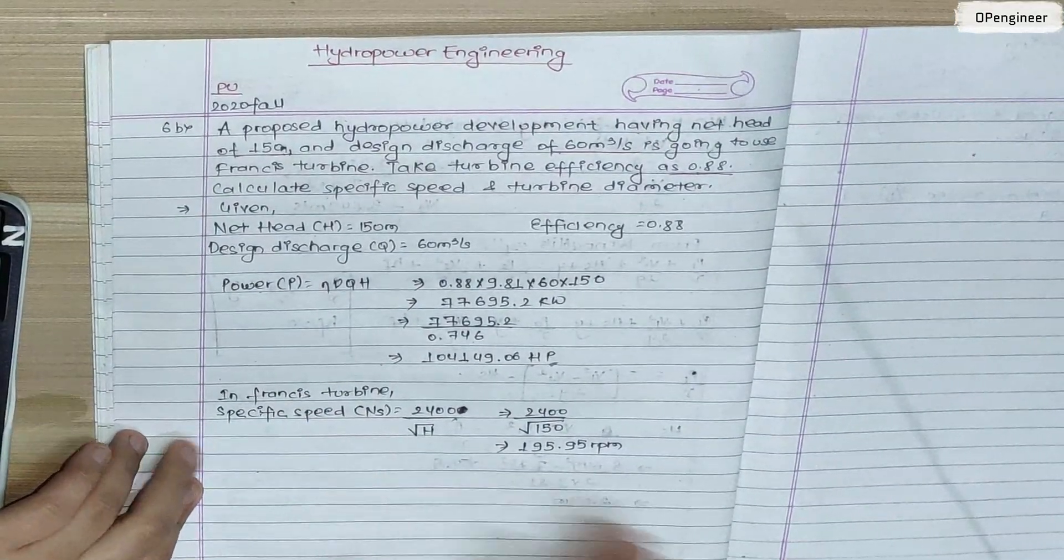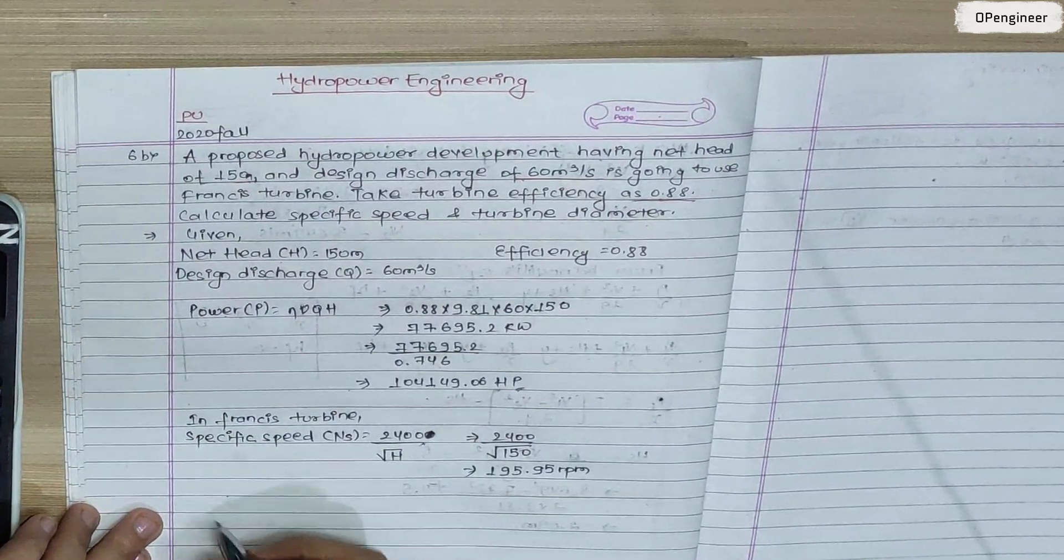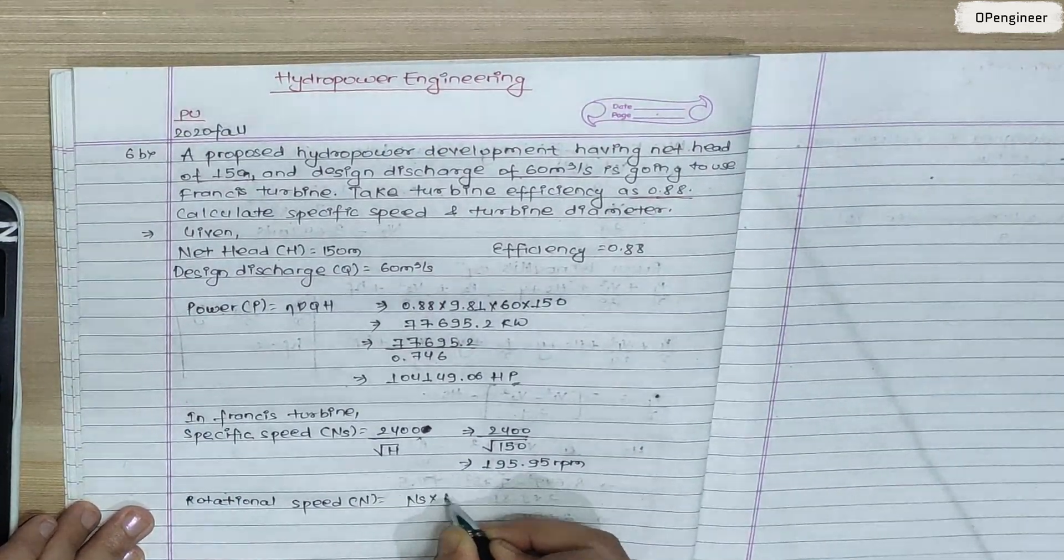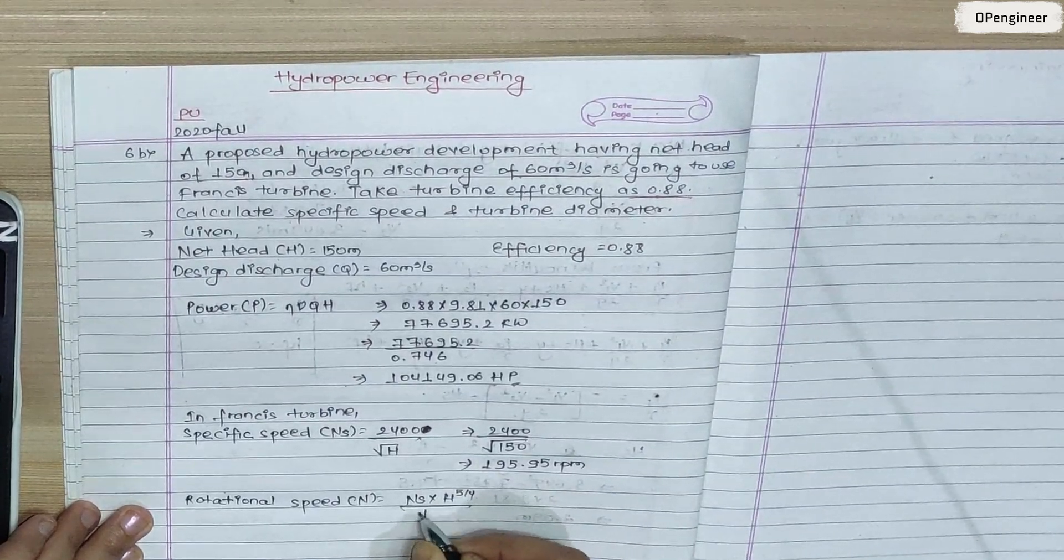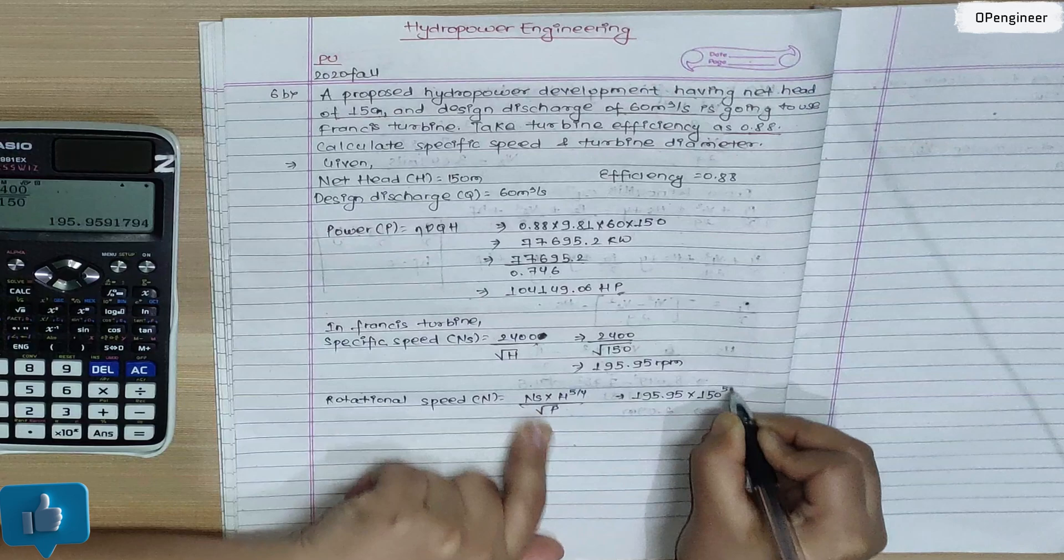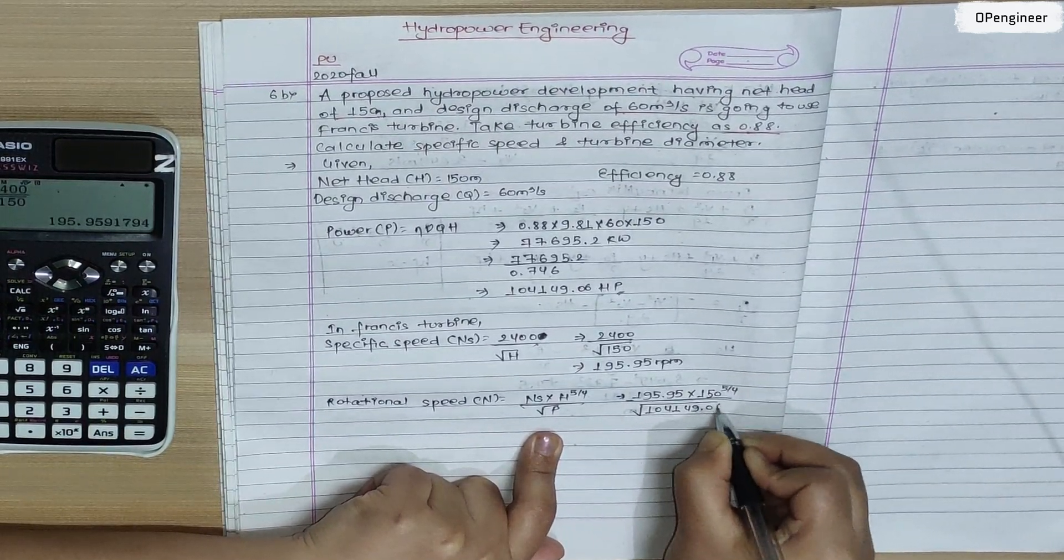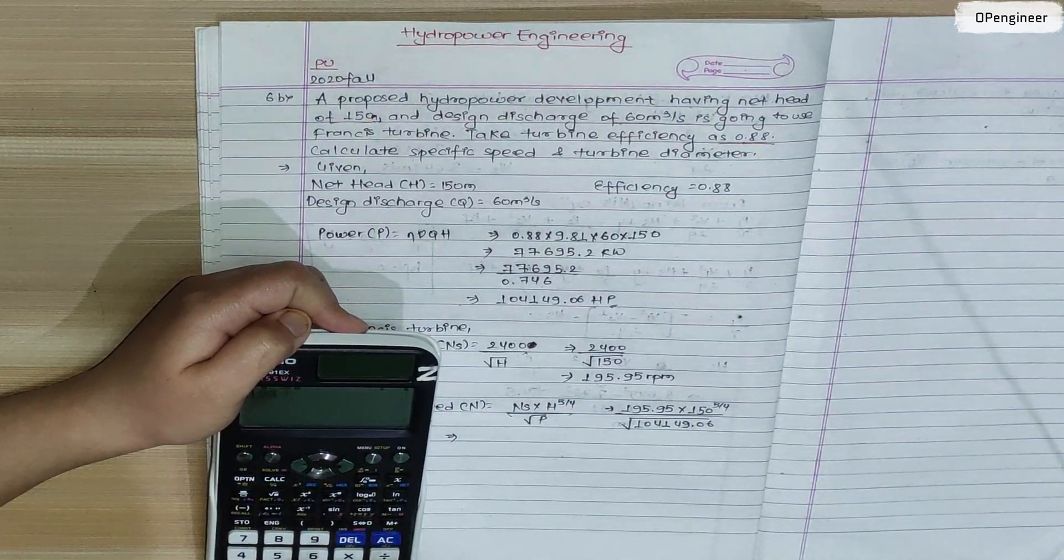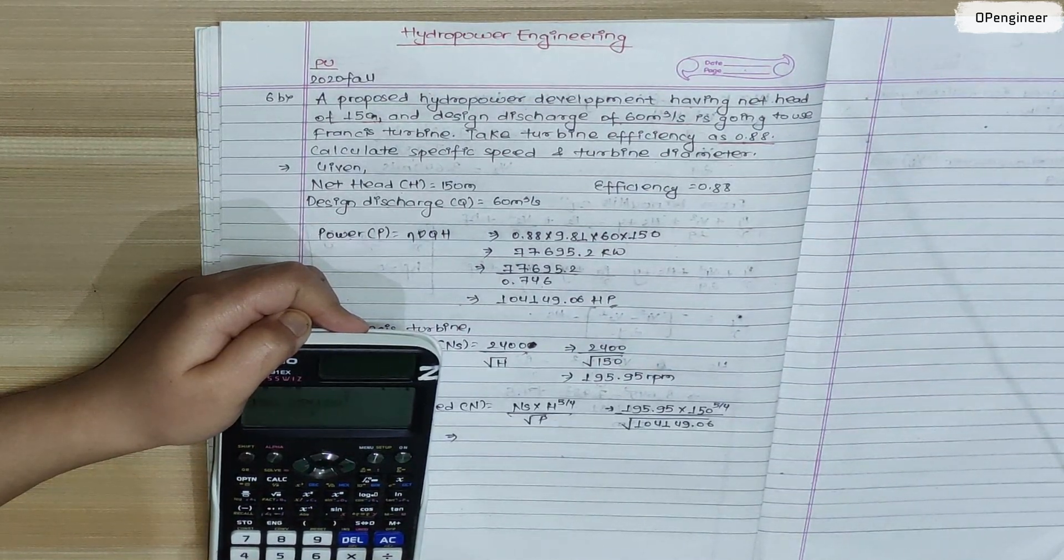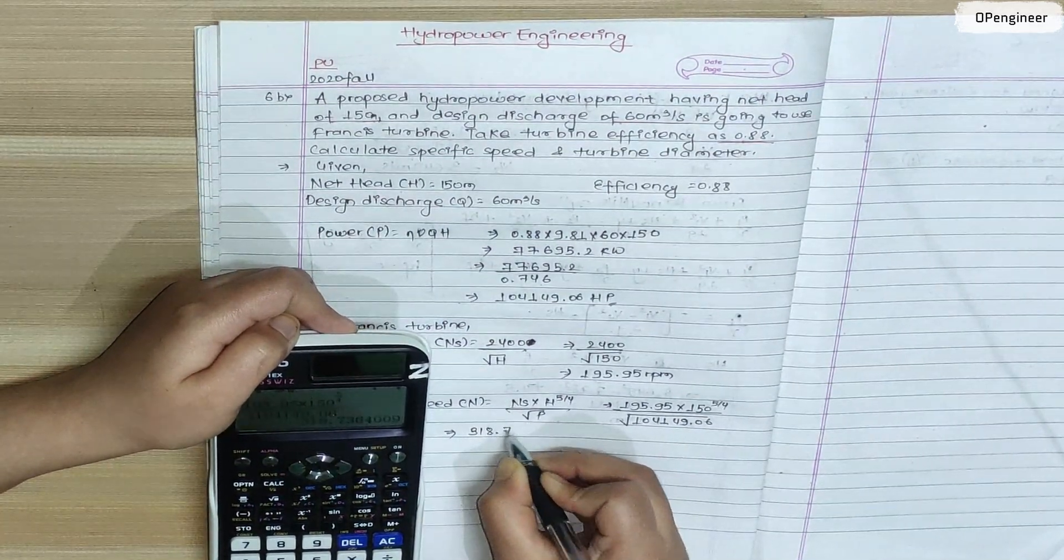If we have specific speed, we can calculate rotational speed. The formula is specific speed into head to the power 5 by 4 over root P. So 195.95 into 150 to the power 5 by 4 upon root over power 104,149.06. Calculate: 195.95 into 150 power 5 by 4 root over 104,149.06, and this is 318.73 RPM rotational speed.